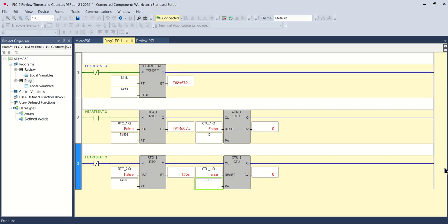And you can see that the one is counting the 1 second intervals on our heartbeat, and the other one's counting the 3 second heartbeat. And between the two of them, they're tracking 2 different sets of time, so that you can then use that for maintenance or for production run reports. There's a lot of other applications for it, but those are kind of the 2 primary ones. If you've run something for a period of time, you want to add something to execute because of that. Or if it's not being run for a certain period of time, you want to execute something.